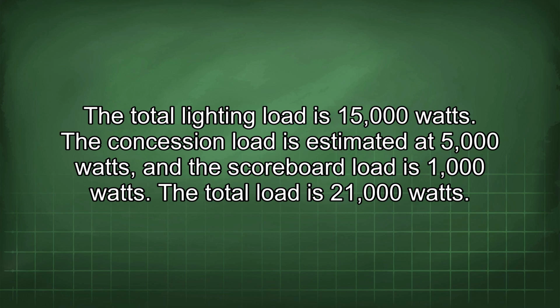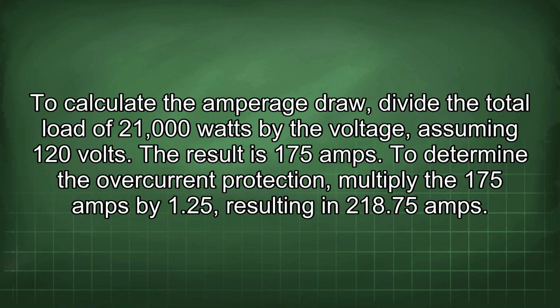The concession load is estimated at 5,000 watts, and the scoreboard load is 1,000 watts. The total load is 21,000 watts. To calculate the amperage draw, divide the total load of 21,000 watts by the voltage, assuming 120 volts. The result is 175 amps.